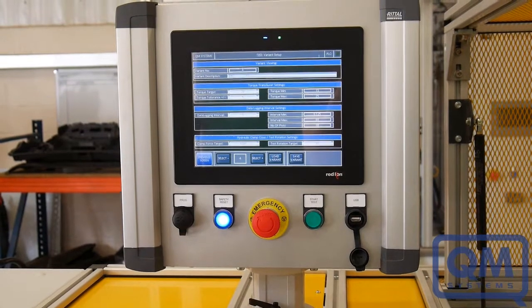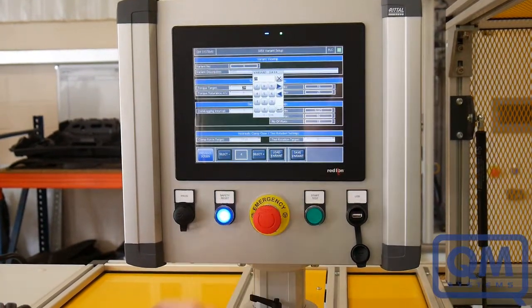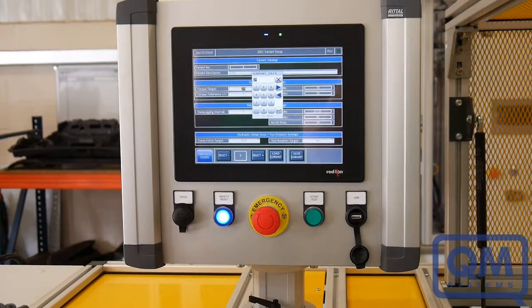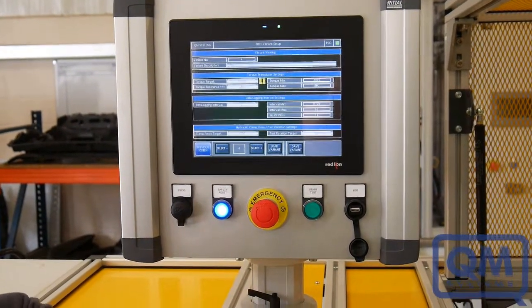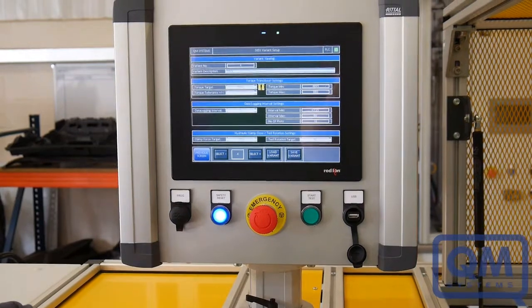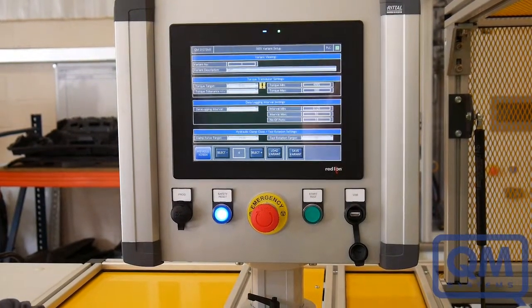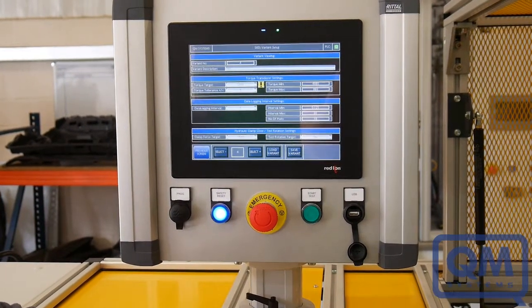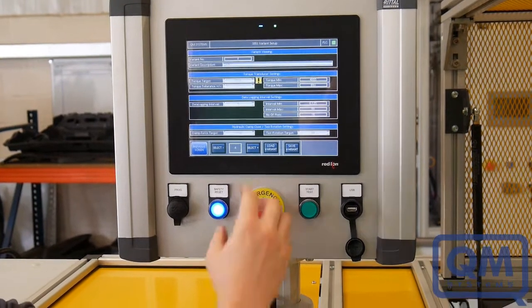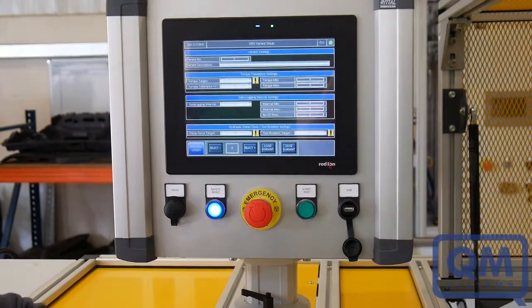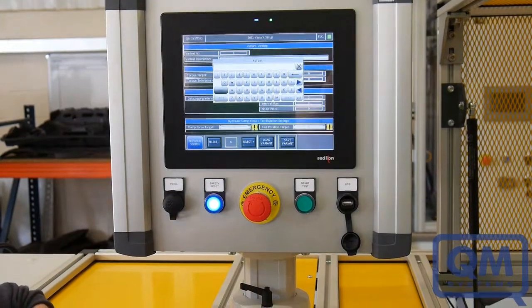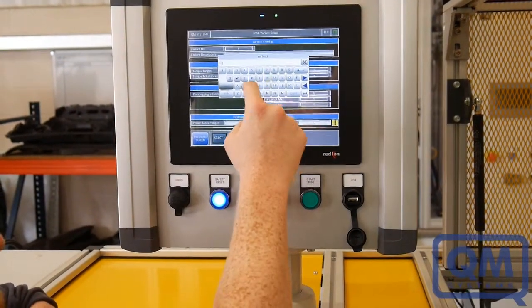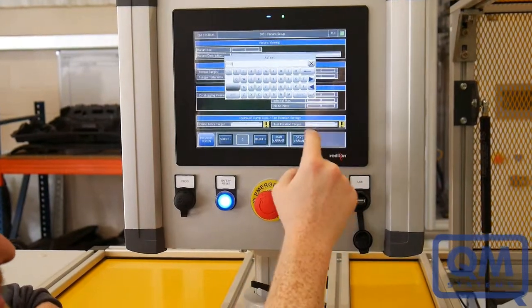Whenever you go over a limit, so whenever you go over the maximum torque of the transducer or the maximum rotation that you can achieve, the value should give you an exclamation mark, which will tell you that the variant data is insufficient, it's not happy. On the variant setup, you can save this data, and the reason why I put it in there is just so if you were selecting a new variant and all you want to do is change the description or put a temporary value in there, you can put that string in and you can save the data.